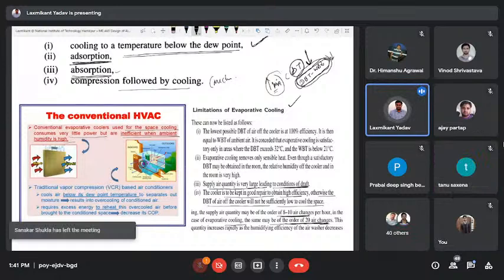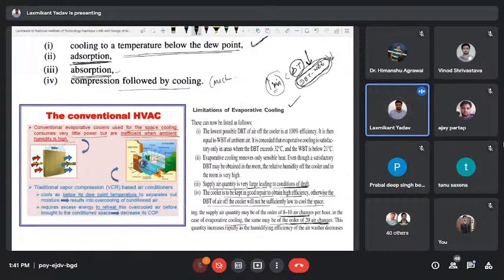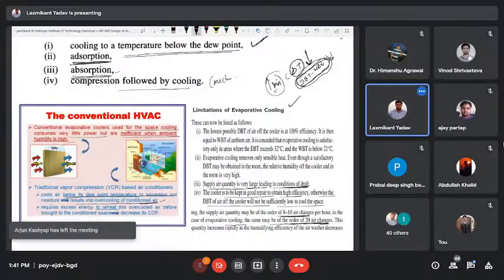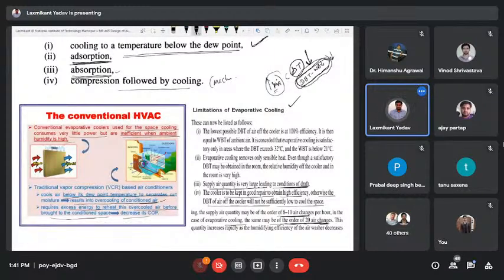In conventional cooling, the air conditioner cools the air below the dew point temperature, and that is also called excess cooling, and again reheating is required. So cooling air below its dew point temperature to separate out the moisture results in overcooling of the conditioned air. So in the case of the conventional system, that is the excess cooling. It requires excess energy to reheat this overcooled air before it is brought to the conditioned space, which decreases its COP.